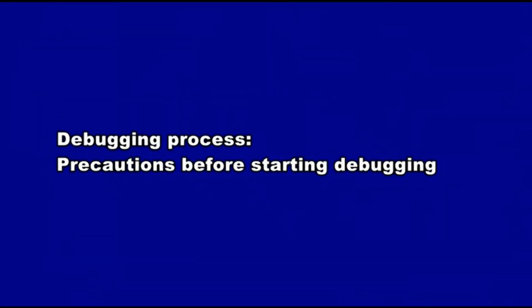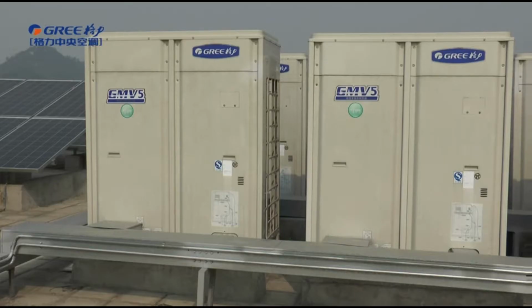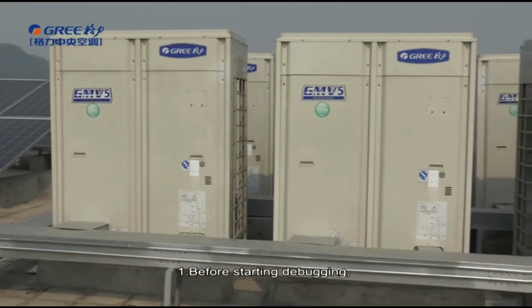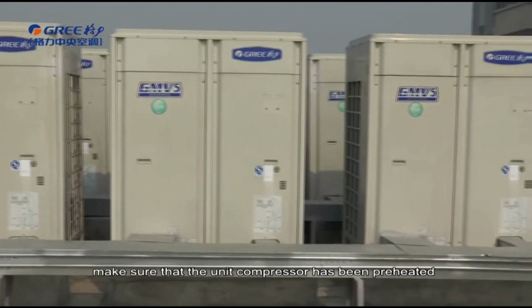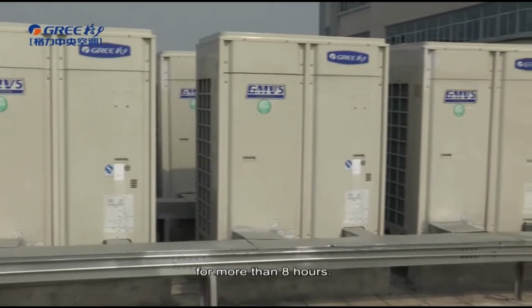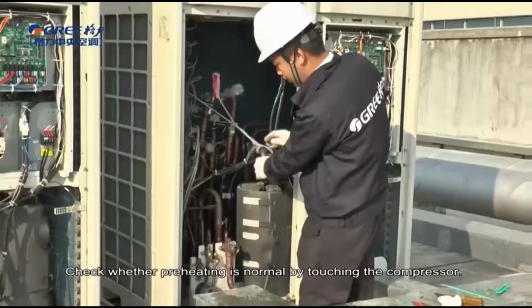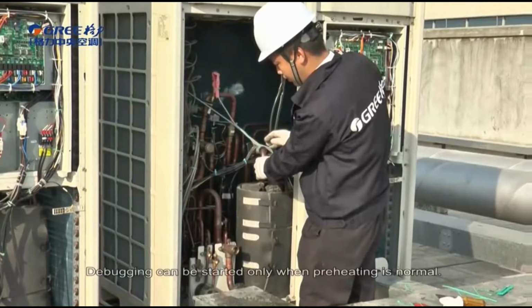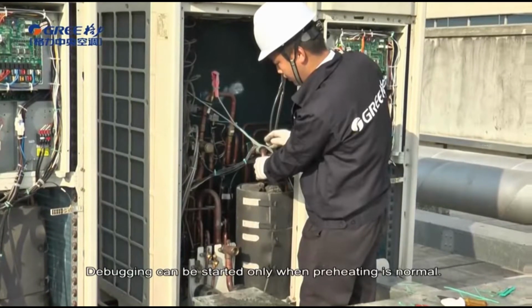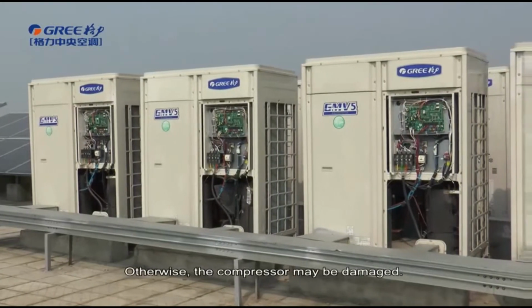Debugging process. Precautions before starting debugging. Before starting debugging, make sure the unit compressor has been preheated for more than 8 hours. Check whether the preheating is normal by touching the compressor. Debugging can be started only when preheating is normal. Otherwise, the compressor may be damaged.